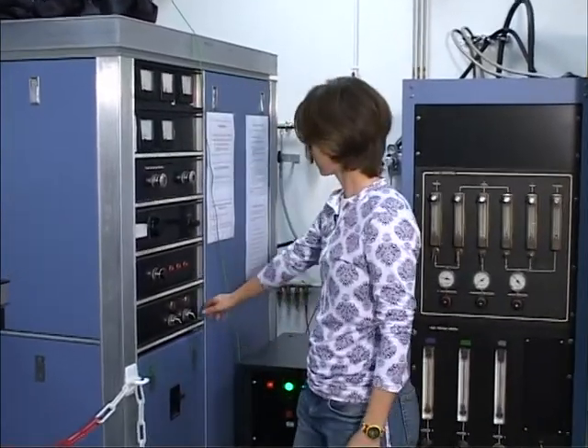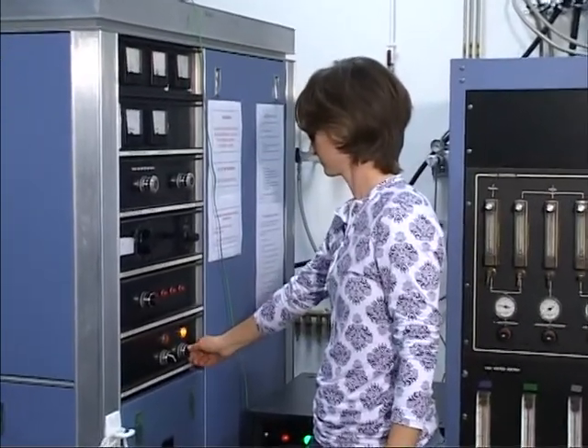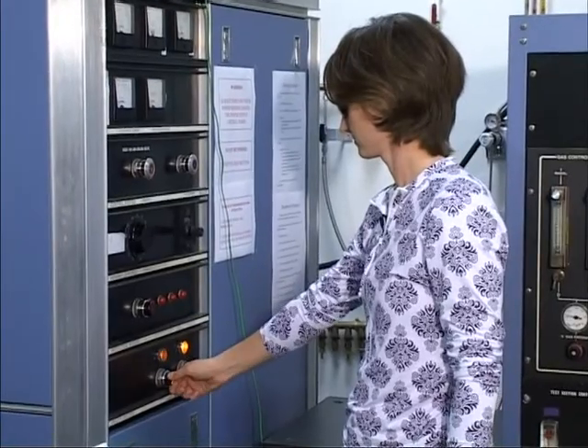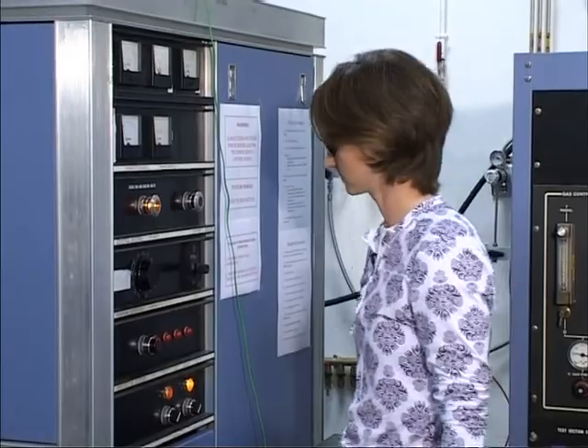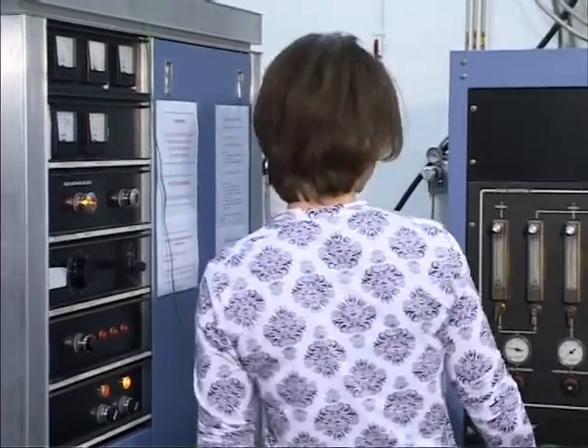To start the torch itself, we turn on the power supply, start the cooling water flow, and turn on the oscillator tube. While waiting for the power supply to warm up, we start the flow of argon through the coil.